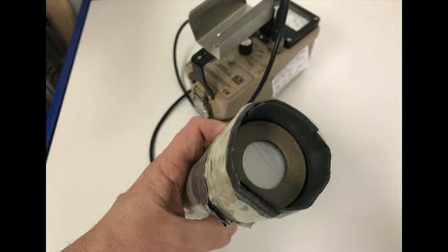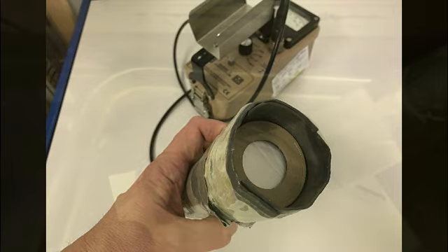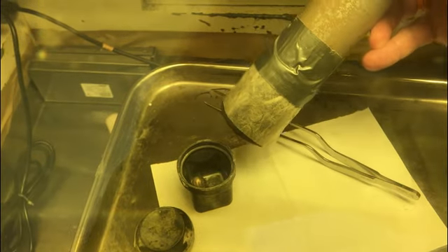Here is one that has a sodium iodide crystal in it, and you can see that then it's very sensitive to the low energy photons that are emitted, for example, from a brachytherapy seed. So they're good for finding those seeds.